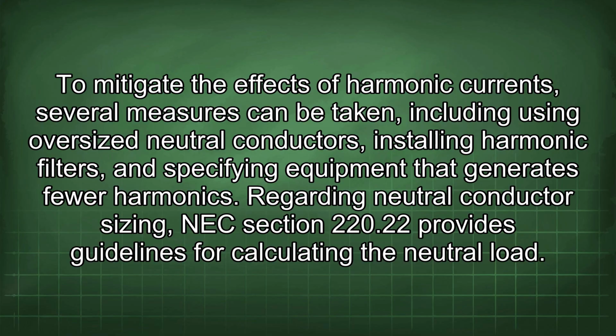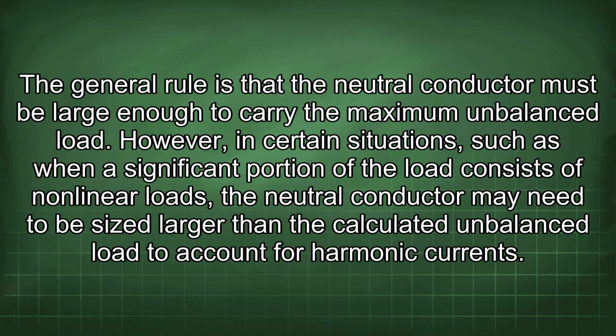Regarding neutral conductor sizing, NEC section 220.22 provides guidelines for calculating the neutral load. The general rule is that the neutral conductor must be large enough to carry the maximum unbalanced load. However, in certain situations, such as when a significant portion of the load consists of nonlinear loads, the neutral conductor may need to be sized larger than the calculated unbalanced load to account for harmonic currents.